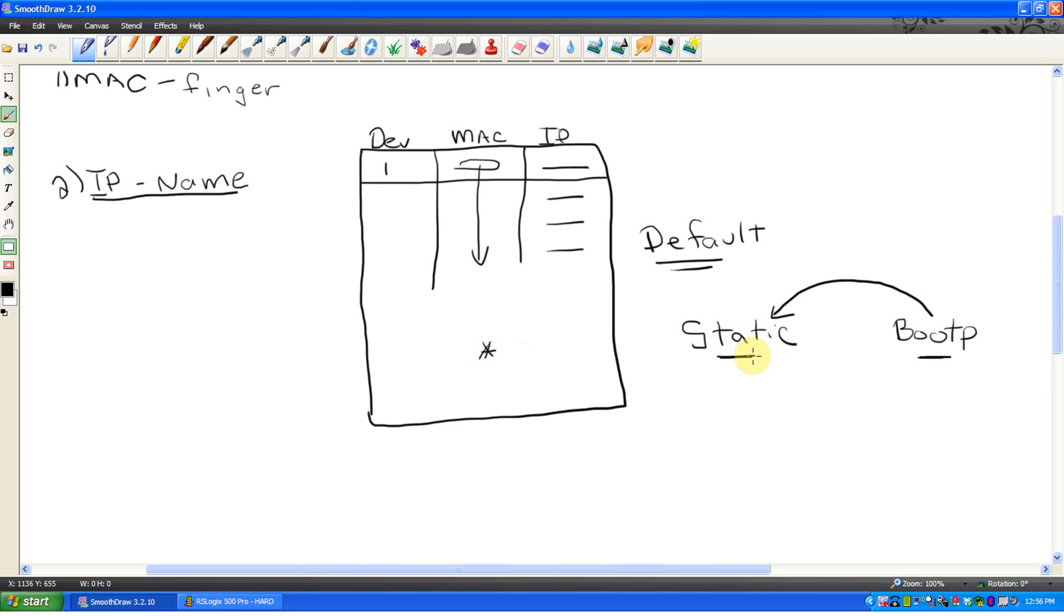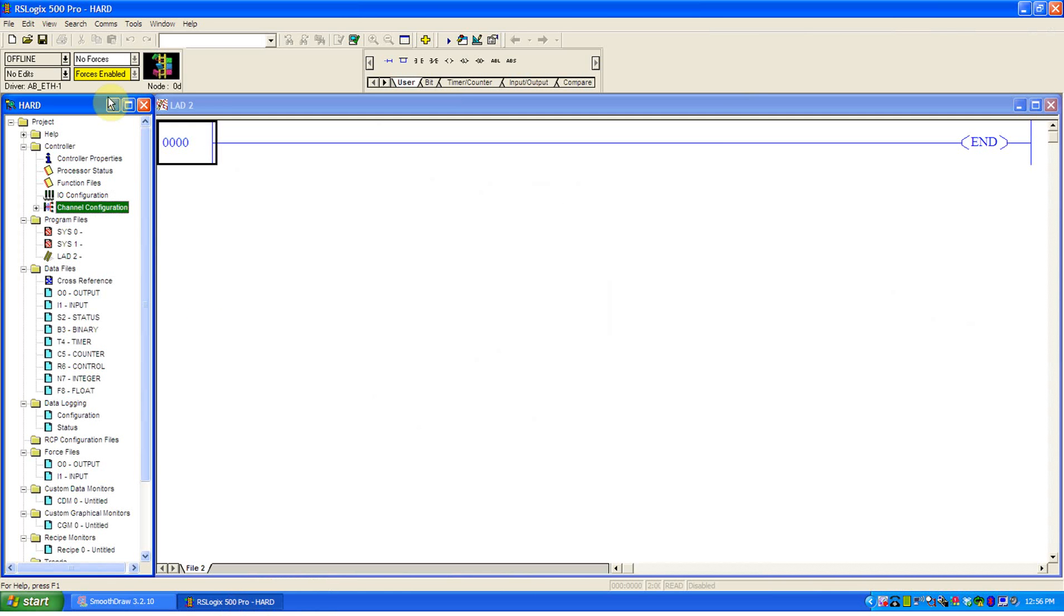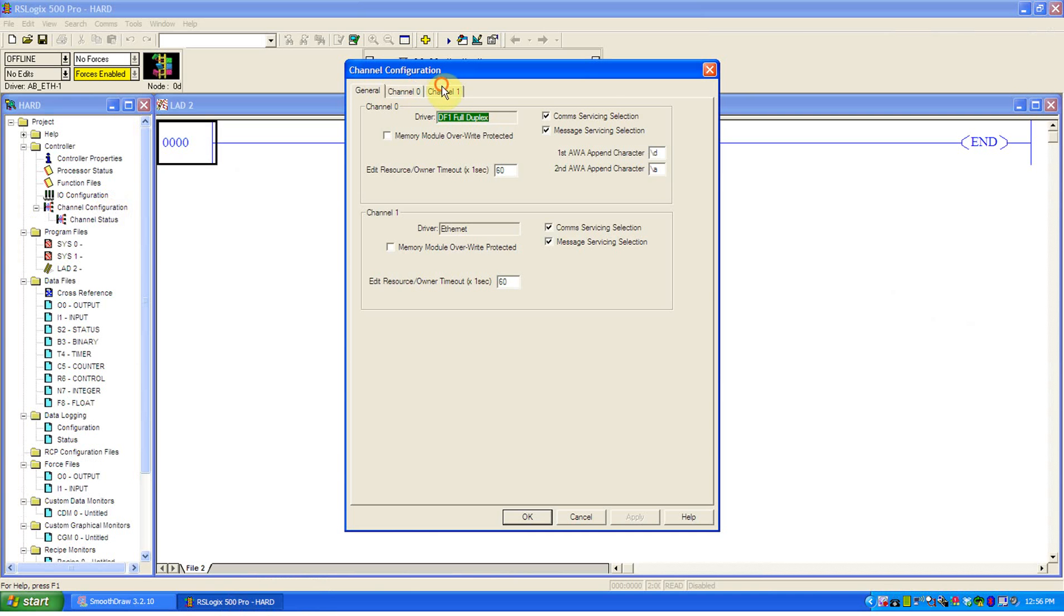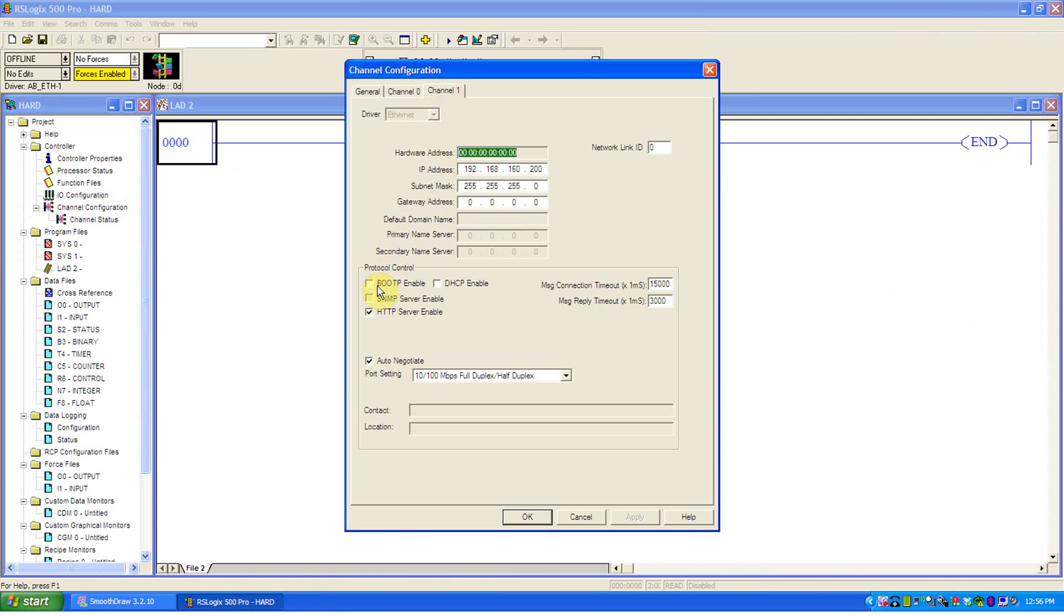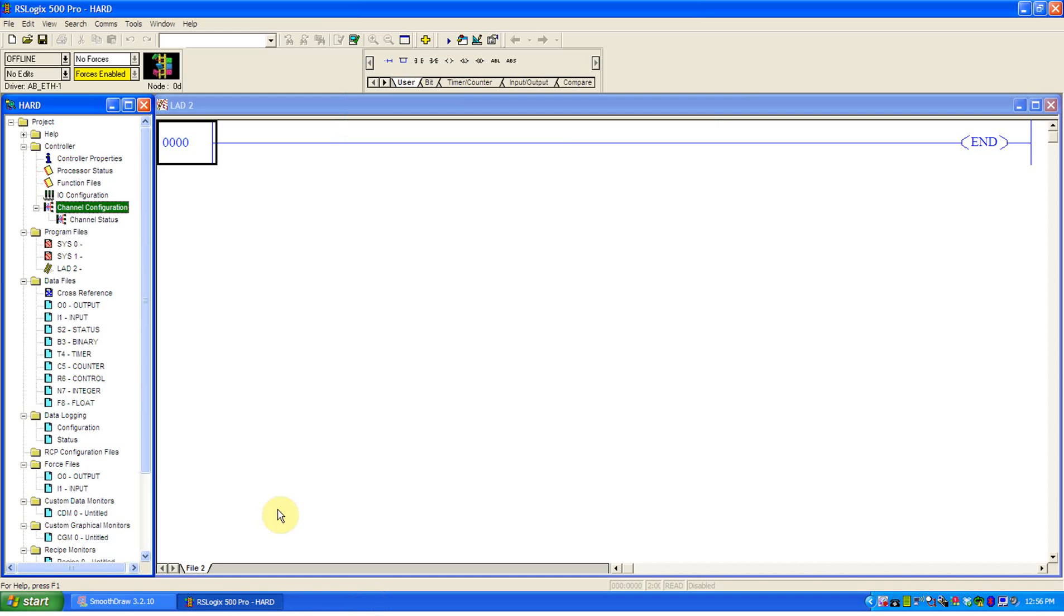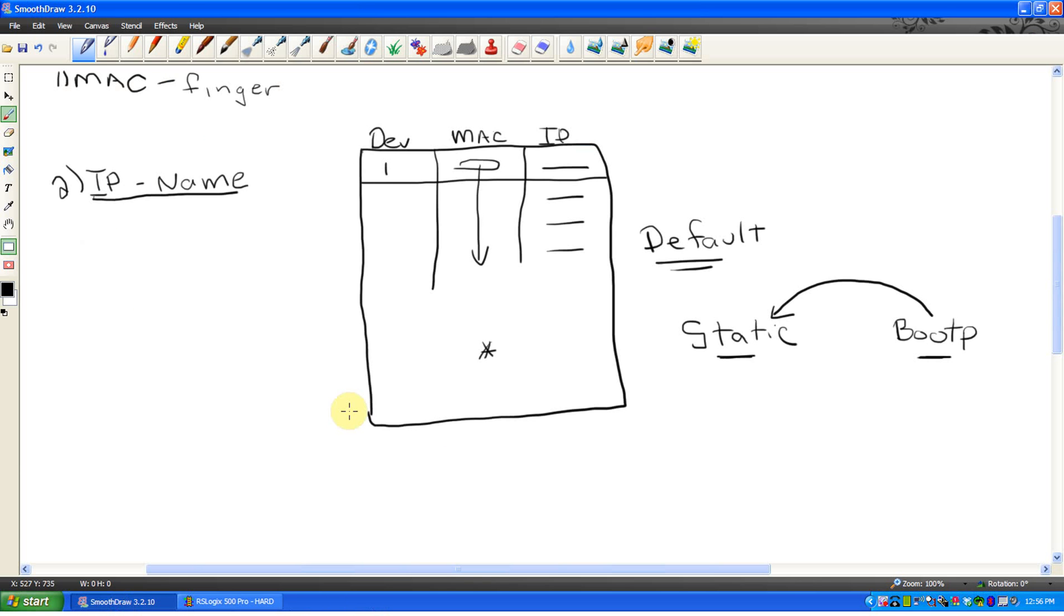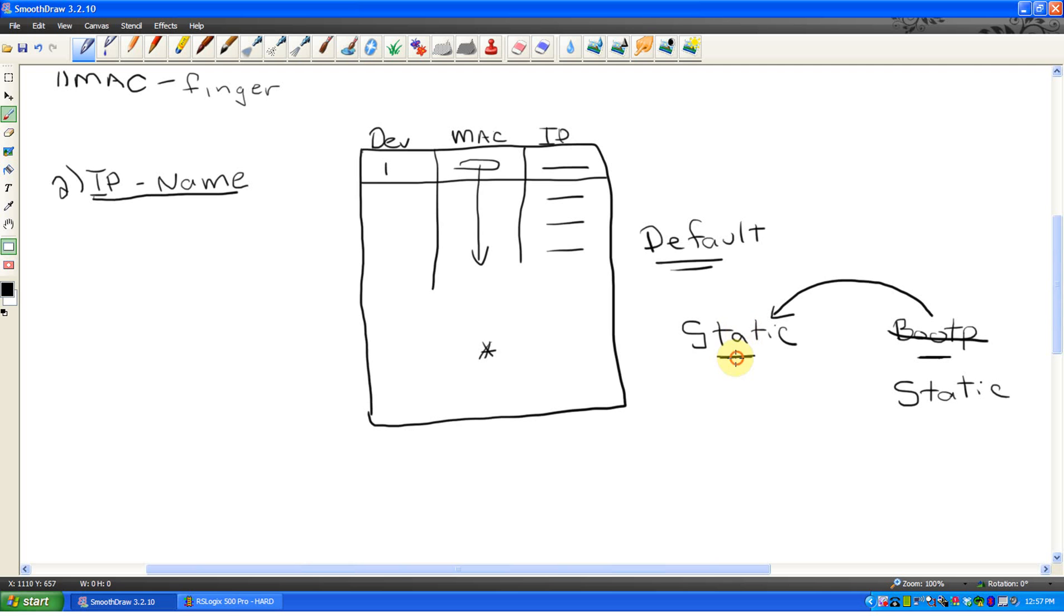But if you don't want to see that apply don't apply option then you can create a template program like this. Go in, create a new program, go into channel config channel 1 and say I don't want boot P. Deselect it, I want you to just have this address all the time. Now when you hit OK, that becomes how this software is set up. When you try and download it you've now changed this to static and they both have the same IP address. So when I attempt to download my program now the PLC says oh well what you're giving me is the same as what I have for communications, no changes, I won't ask all these crazy questions about apply and don't apply.